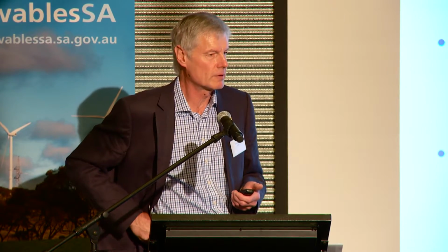And at the bigger scale, then you can use gas turbines, because gas turbines have one great advantage over the spark ignition engines, and that is from the exhaust gases they can produce steam, and they can produce steam at far higher process conditions. So if you want high pressure steam, high temperature steam for a particular use, then you put a gas turbine engine on rather than the spark ignition engine. And so it really depends on what you're actually looking at and how you integrate your AD process into a bigger process.